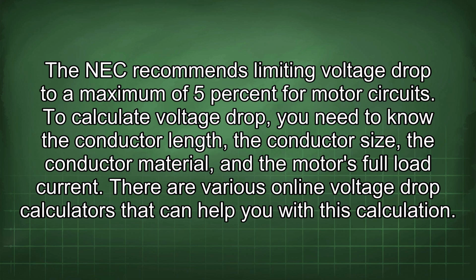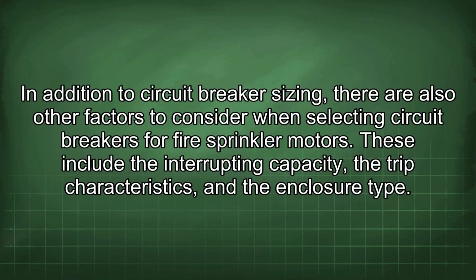To calculate voltage drop, you need to know the conductor length, the conductor size, the conductor material, and the motor's full load current. There are various online voltage drop calculators that can help you with this calculation. In addition to circuit breaker sizing, there are also other factors to consider when selecting circuit breakers for fire sprinkler motors. These include the interrupting capacity, the trip characteristics, and the enclosure type.